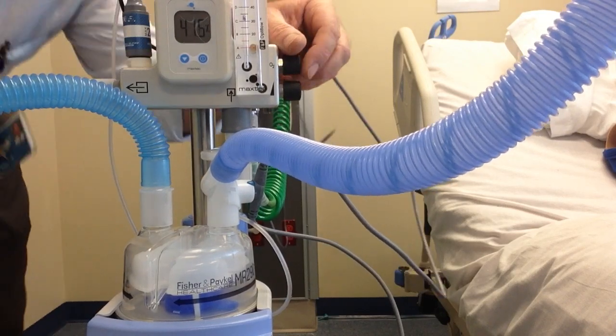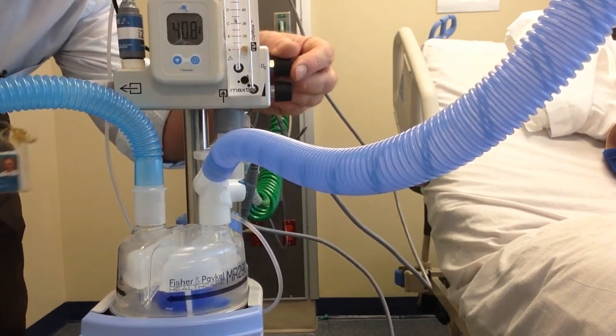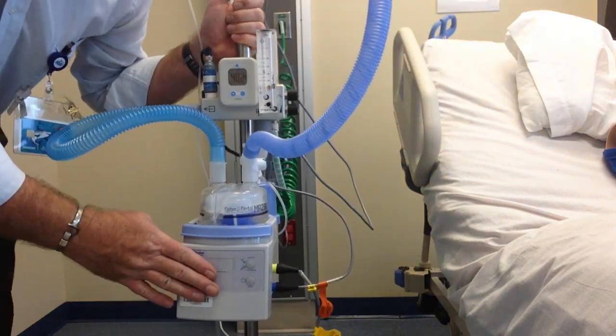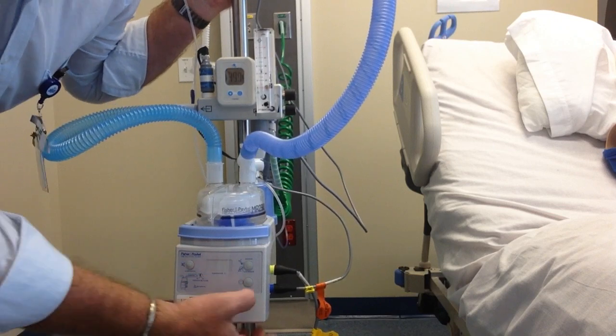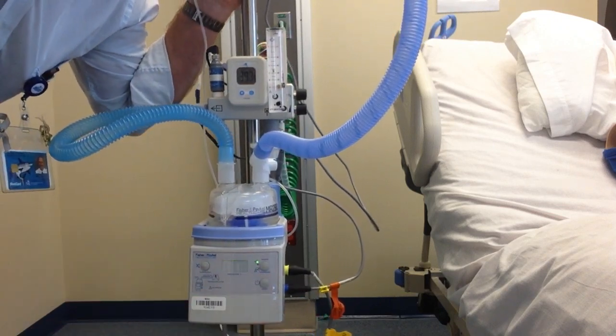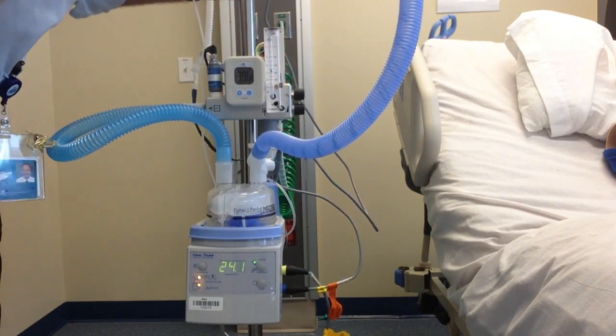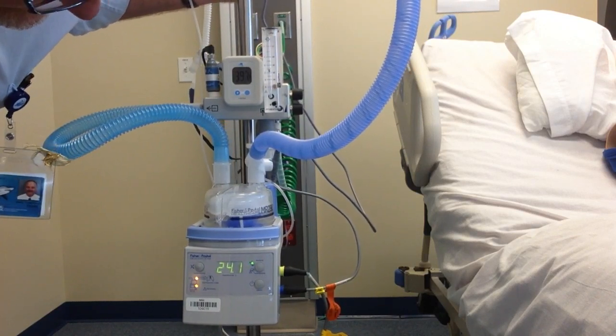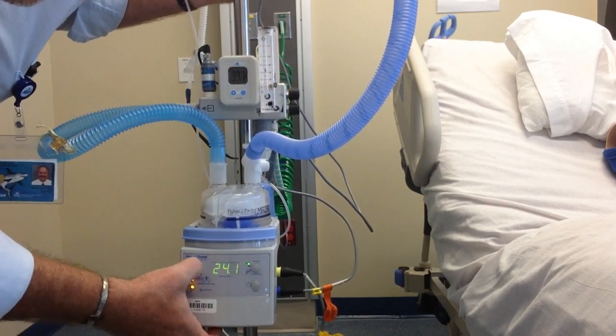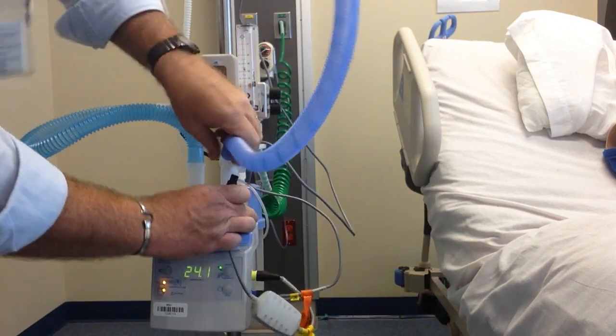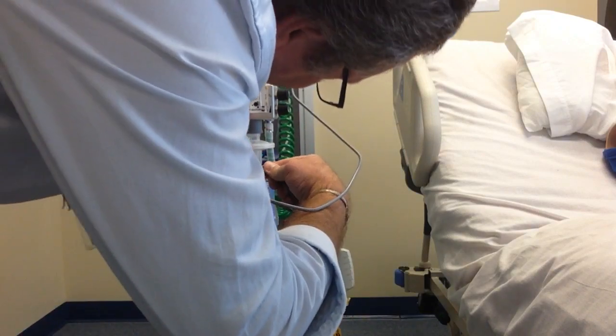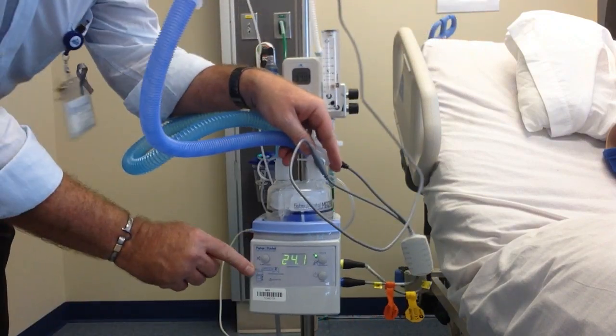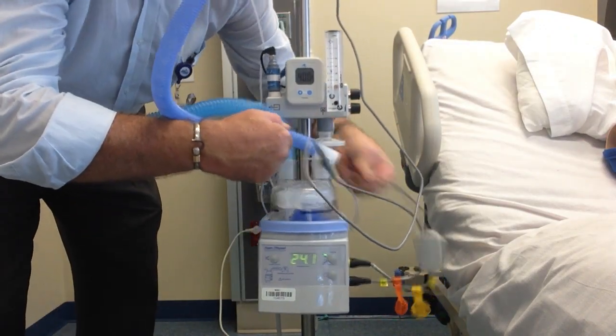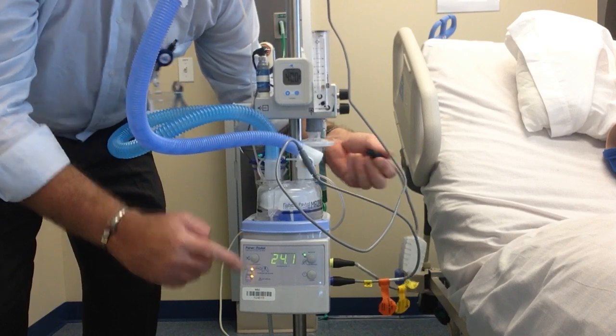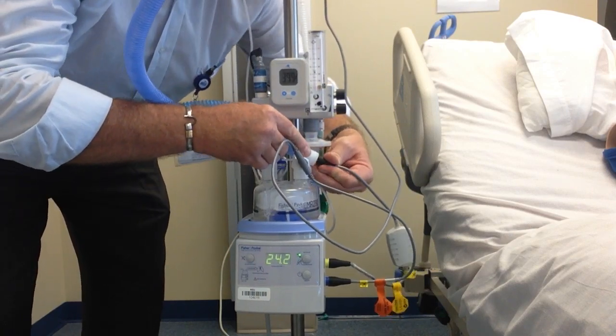And it's just a matter of titrating and playing with the FiO2 knob until you hit 40%. The other question is, how does this work? Well, you have an on-off switch right here on the bottom. It says on-off. Turn it on. What this is telling me is that I have no, I'm going to silence it. I have an alarm. This thing is not hooked up. So this tries to make it foolproof for you. There. If you notice, my alarms went off. When that was not hooked up, it's alarming. It'll flash. I hook it up, so it's telling me now you're set up.